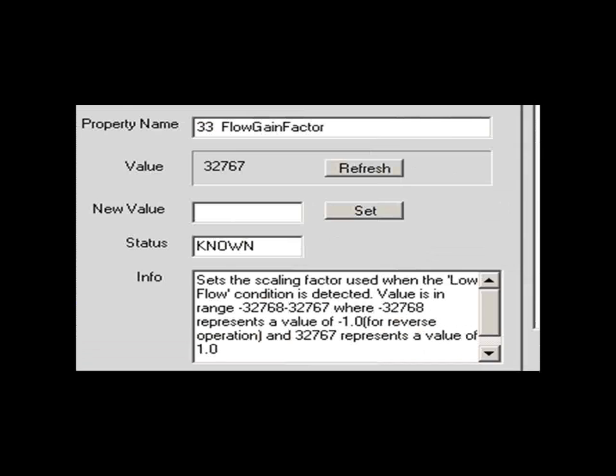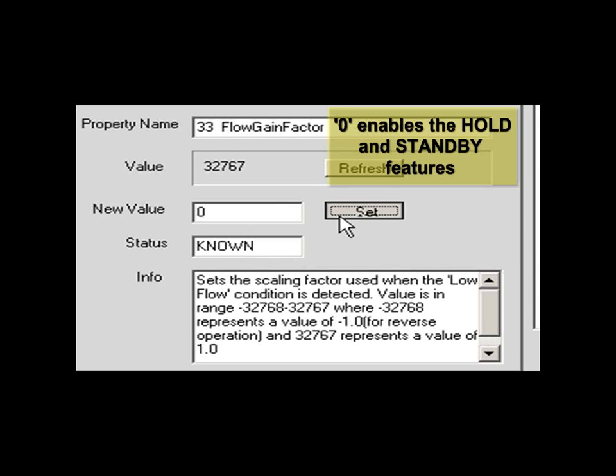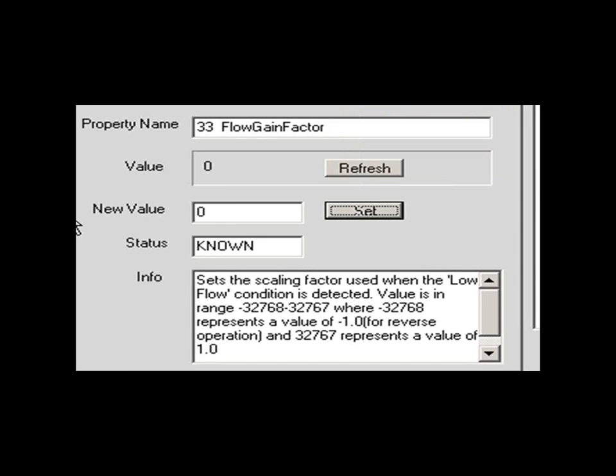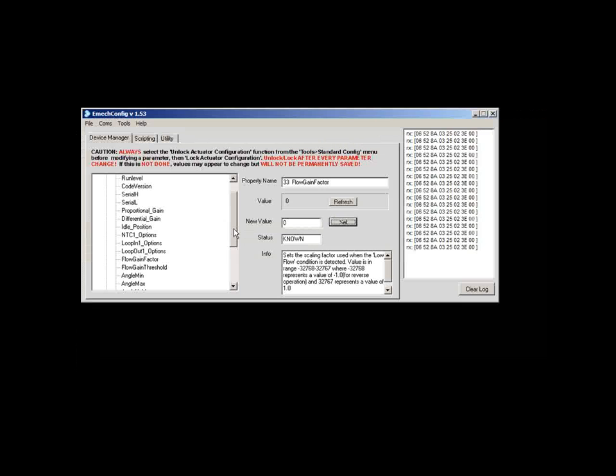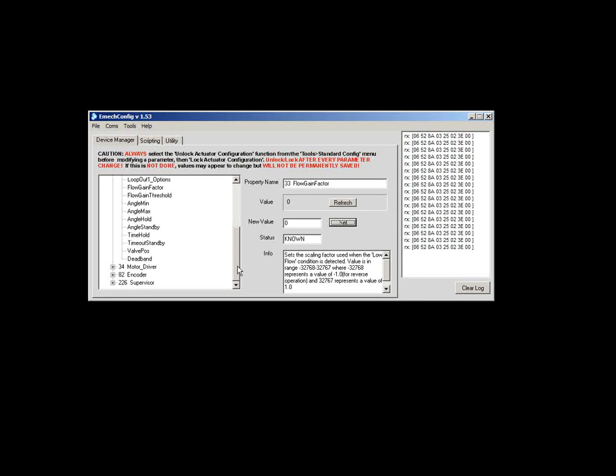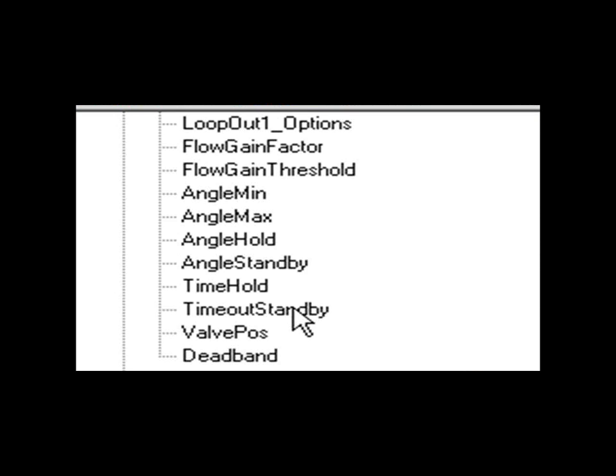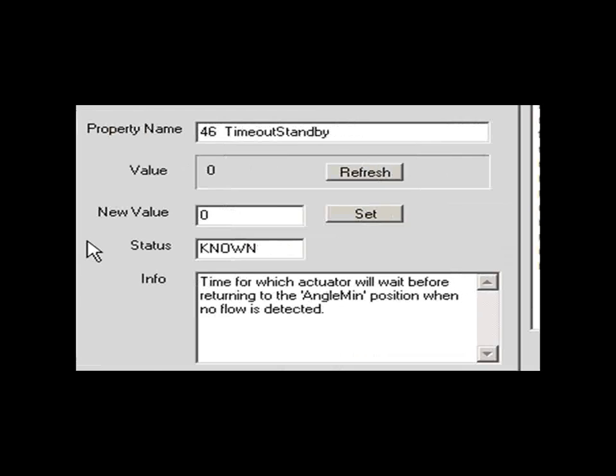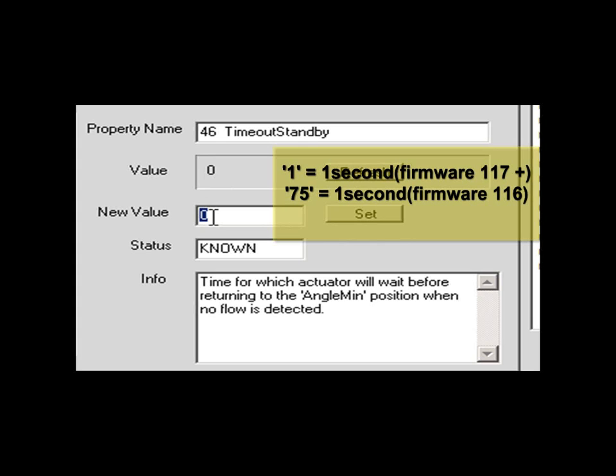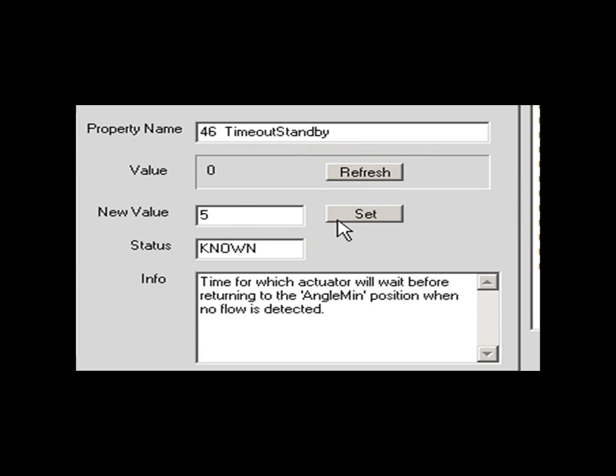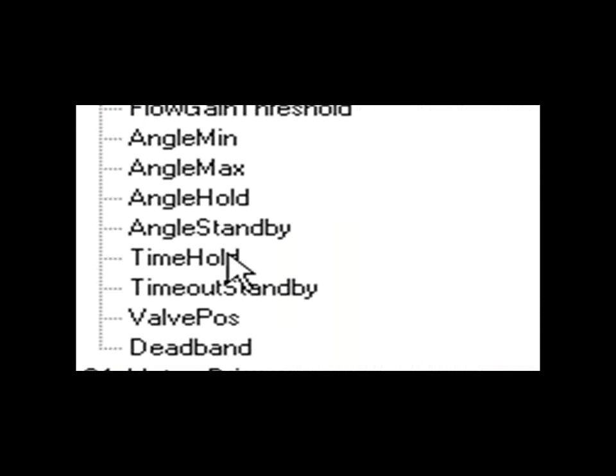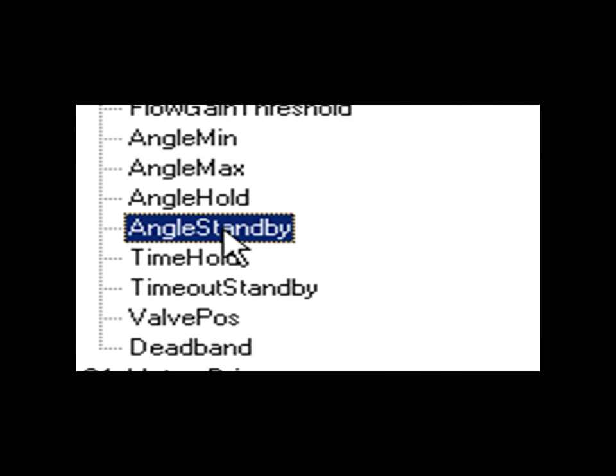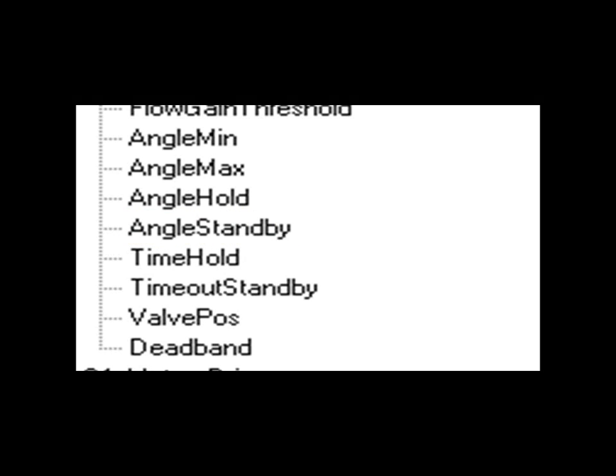Move down and select the flow gain factor. Give it a value of 0. This will enable the hold and standby features. Move to the left and select timeout standby. In this example, I'm giving it a value of 5 seconds. Move to the left and select angle standby. In this example, I'm giving it a value of 0, which is equivalent to 0 degrees.